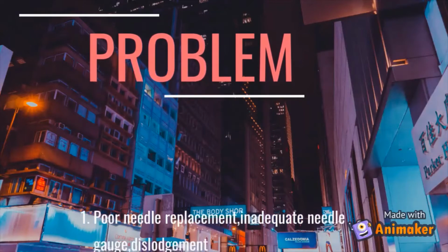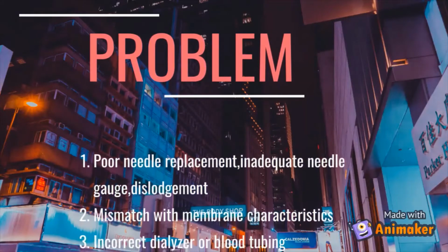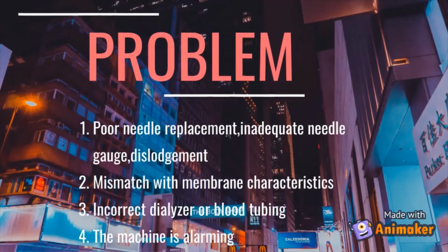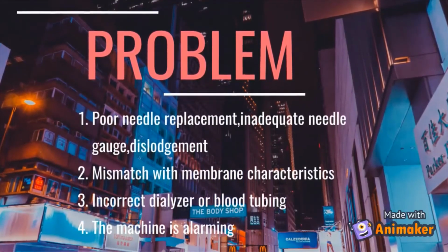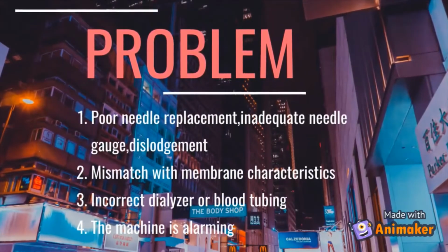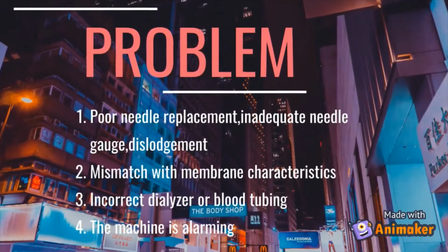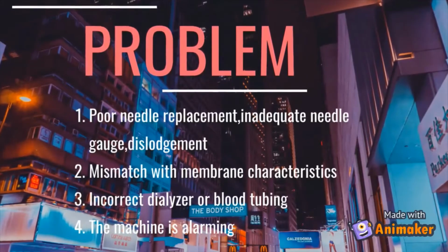The problems faced: firstly, poor needle replacement, inadequate needle gauge, dislodgement. Secondly, mismatch with membrane characteristics. Third, incorrect dialyzer or blood tubing. Fourth, the machine is alarming.